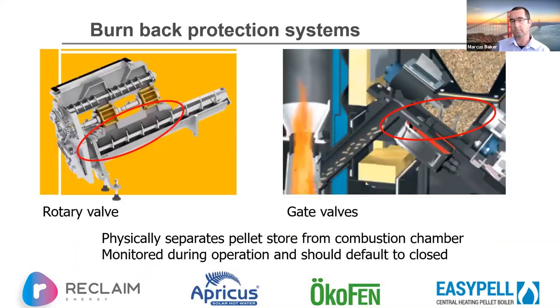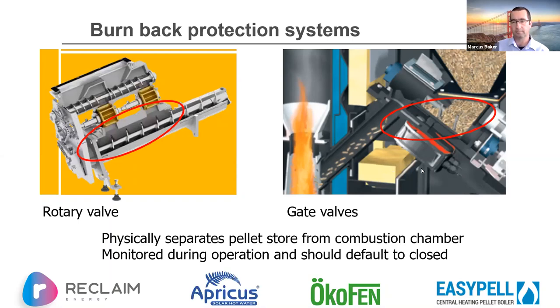Once pellets are in the boiler, burnback protection is critical — the last thing you ever want is for fire to get into your day hopper. Every pellet boiler must have a very effective means of preventing that, preferably multi-stage with layers of redundancy, automated so that if there's a power cut the default position is closed and it must actively be opened.